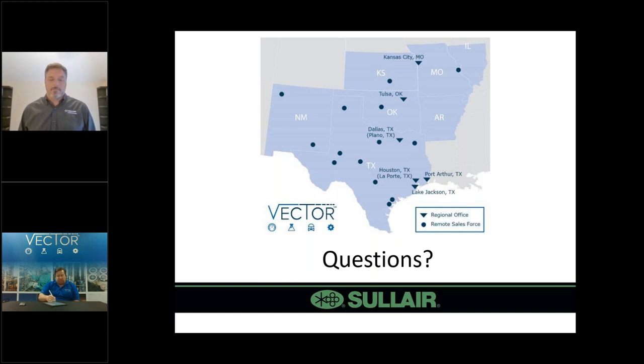Next question: do we have to replace the piping to remove the contamination if we switch to an oil-free system? That's up to the customer's tolerance for contamination. If they have a real contamination problem and the piping is old — say 20 years — then yes, if you switch to an oil-free system, you should replace it with clean piping. In some cases, customers just purge the air system for a few weeks by running it and cracking open a few valves to try to get the oil out. Over time the air can clean out the moisture and lubricant. We do recommend changing the piping if possible. But if you have a huge facility where it's not cost-effective, you'll have to continue using point-of-use filtration until the piping is dried out over a few years.